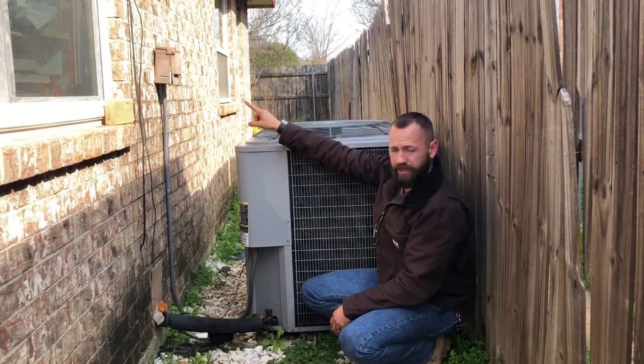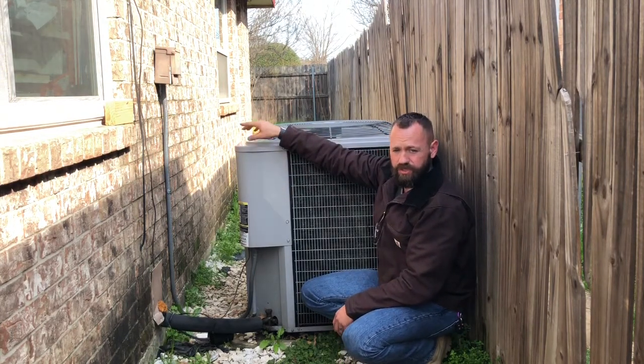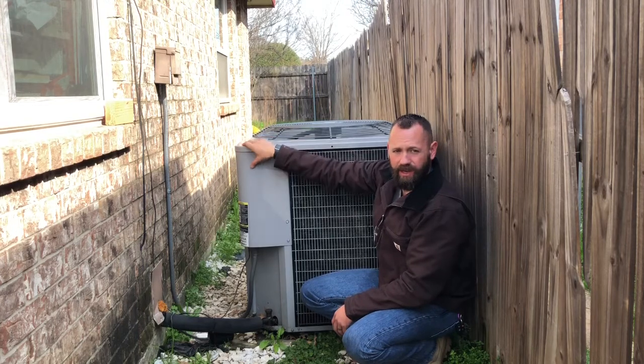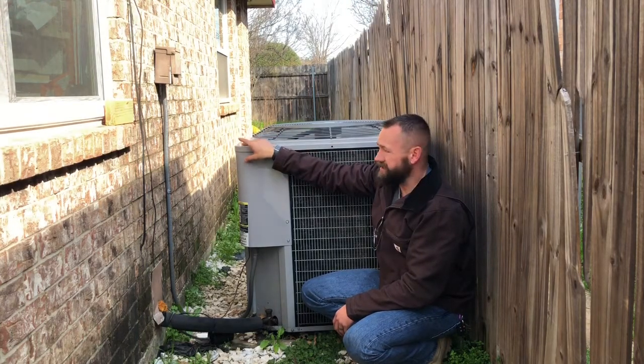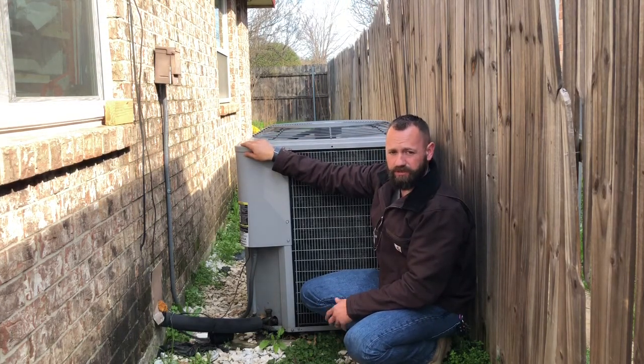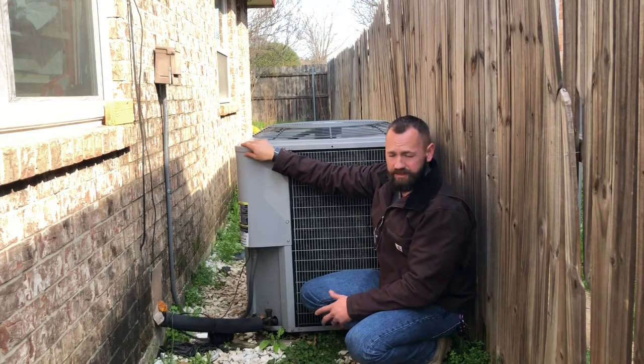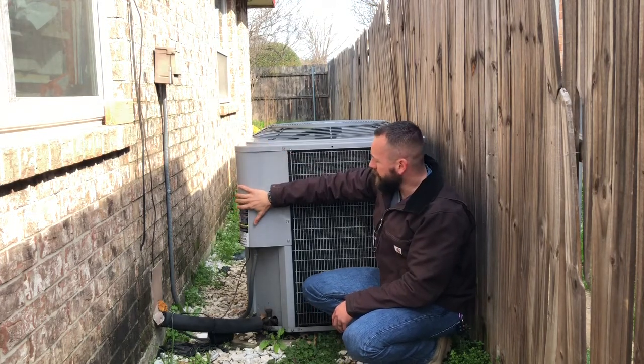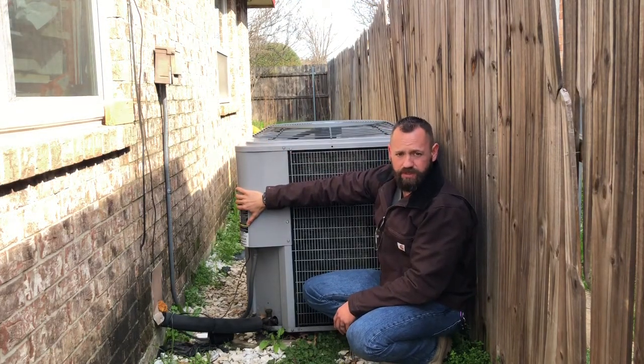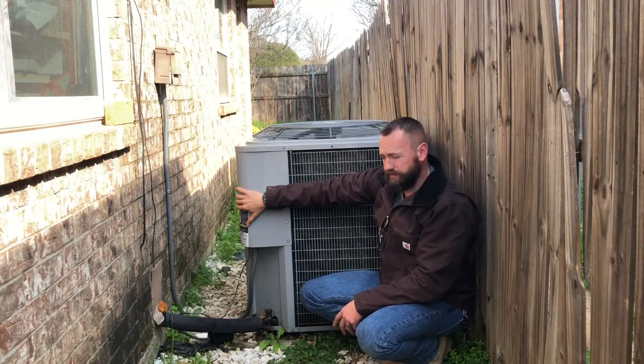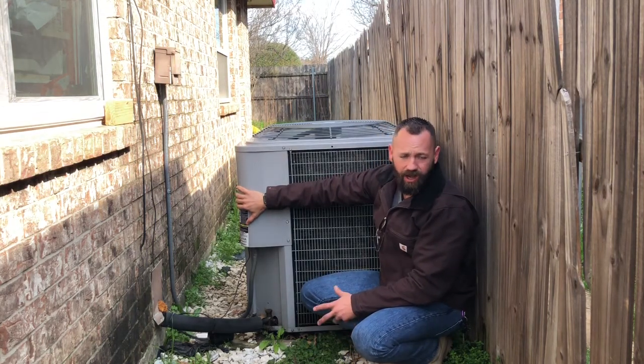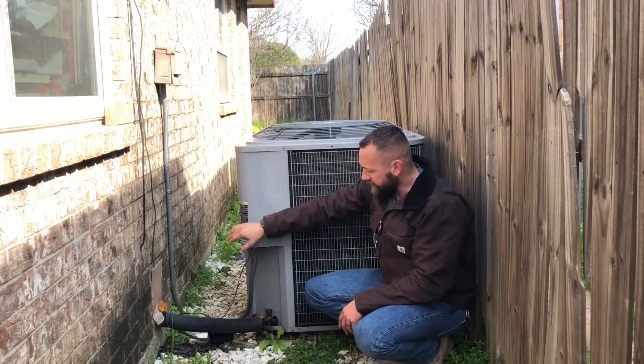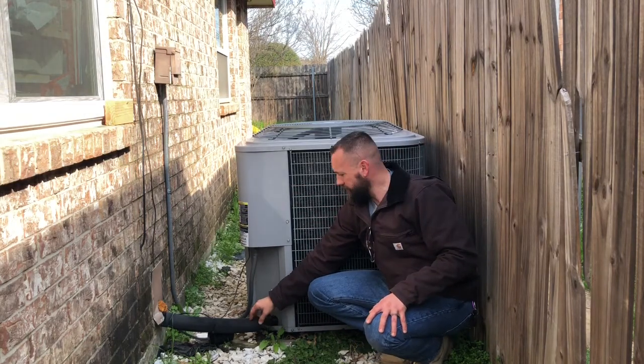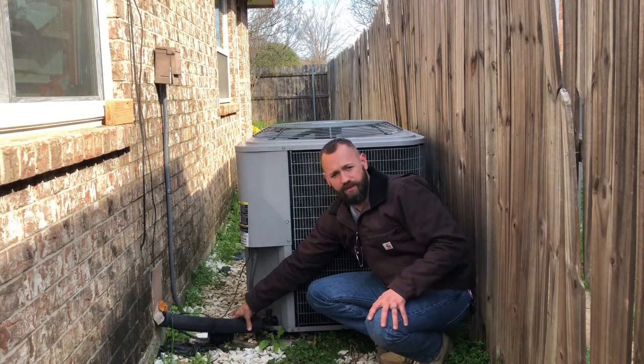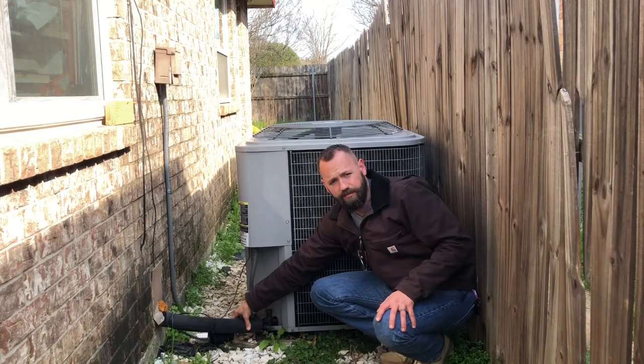Up on the wall up here is your disconnect. So you can shut off power to this unit without having to go to your breaker inside. These disconnects are very important, especially for service and maintenance. Behind here, you have your controls. So this is the electronics that make this condensing unit operate. Then you've got down here at the bottom, like I said, your copper, and you can't see it, but back here is a filter dryer that keeps your refrigerant clean.